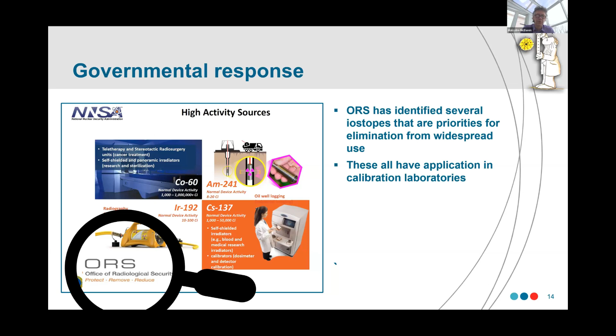They're not a major concern because they tend to be well controlled, and it's not just in the USA. But if you're reducing the sources in these wide applications, then there's a risk to metrology laboratories in that the sources may not be available. And so for us as a calibration community, we are potentially collateral damage to a well-meaning activity to reduce risk in places where sources perhaps can be replaced.